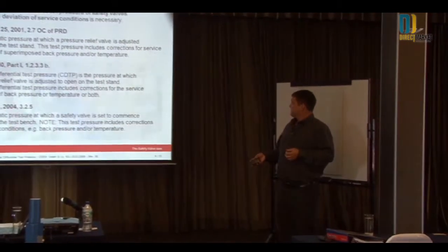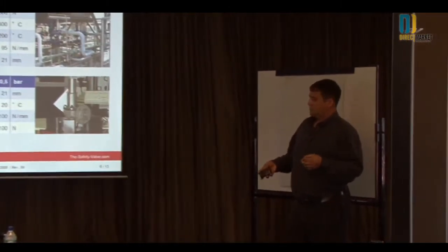So some of the influences on the valve are going to affect the valve while it's in operation, such as back pressure or temperature. When it's in operation, that's a completely different scenario than when you're in your test facility or your maintenance facility and you're working on the valve. The temperature is going to be whatever the temperature is. 20 degrees Celsius, I think, is around normal.